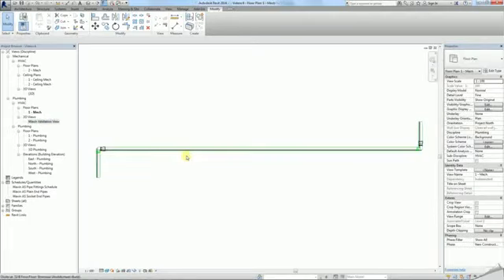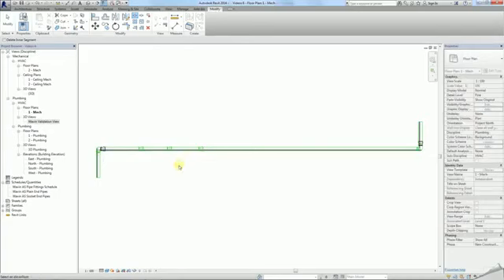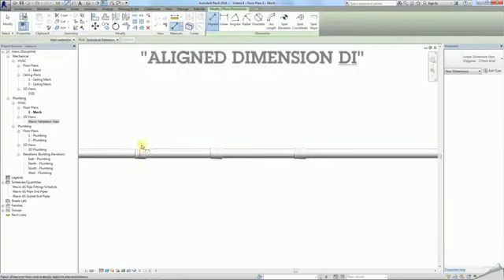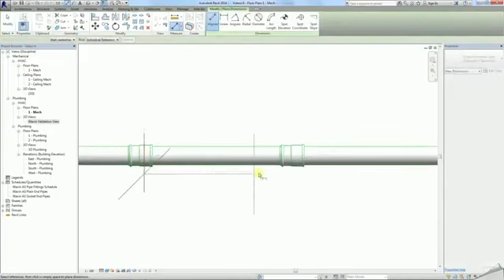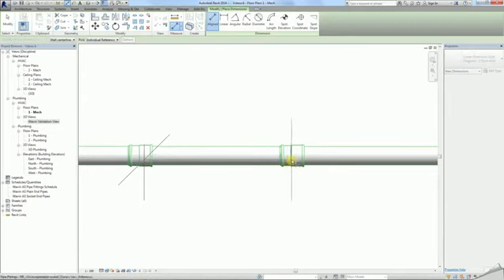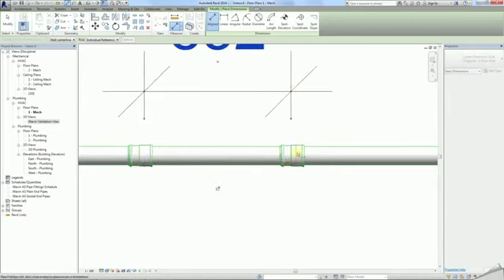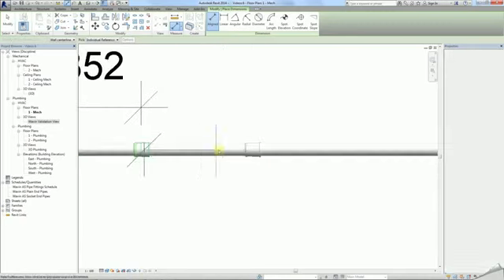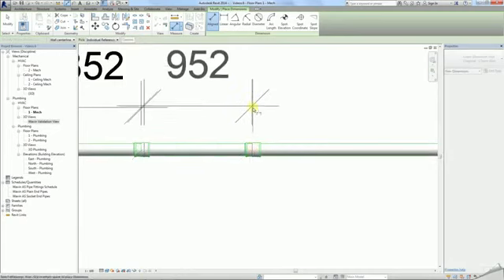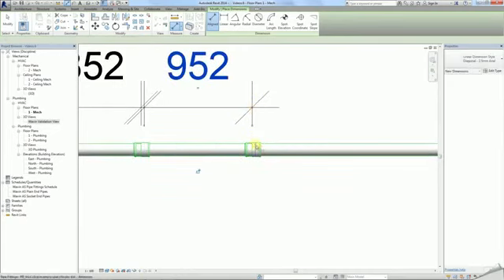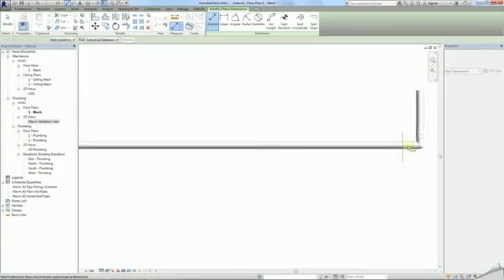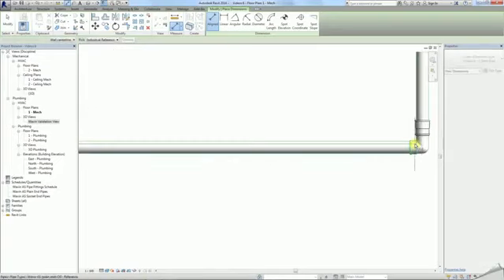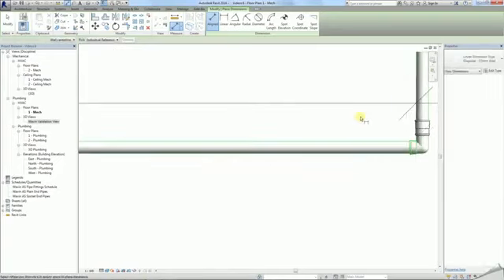The second way is even more precise. Start by placing the splits anywhere on the pipe. Then create an aligned dimension between the fittings. Attach the dimension to the reference points of the couplers, right where the pipe ends. You may need to use the Tab key to select the desired point. If you attach the dimension to the pipes instead of the fittings, the solution will not work.